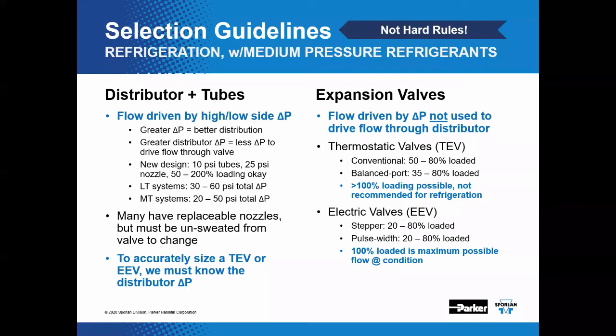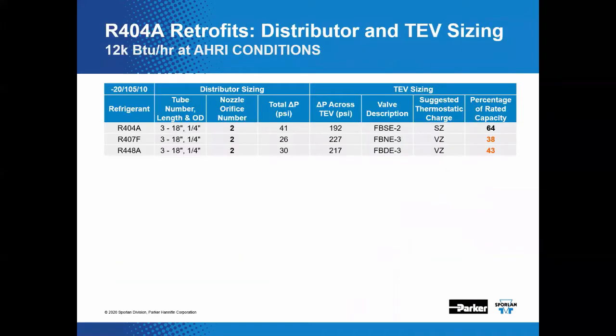Electric valves, we can increase that range to 20 to 80% for both stepper motor driven and pulse width modulating style valves. With electric valves though, 100% loaded is generally considered to be the maximum possible flow through the valve at the conditions specified. There's no reserve built into these products as there is with some of our expansion valve line in the thermostatic range. With some guidelines to follow that we've now put in place, let's jump into a theoretical retrofit.